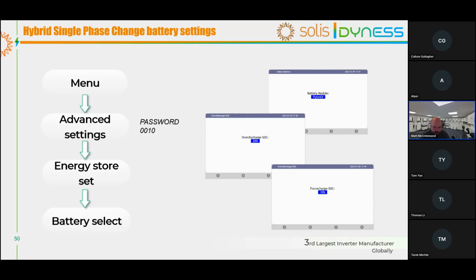The other value that we didn't discuss there is in another setting, and it's called battery reserve, and that's if you have the backup switch. So when we talked about having a critical load, the worst case scenario for you is to have the grid fail at 7 in the morning when there's no PV and you've discharged the battery through all the night, and you don't have available power to supply your critical load. We do have another setting which is called battery reserve. That means that you could set, for example, that to 50%, which means that the battery would then oscillate between 100% and 50% all the time, and then it would leave that between 50 and 20% available for you to discharge when the grid's not available.